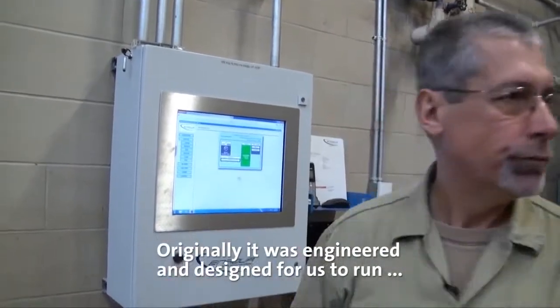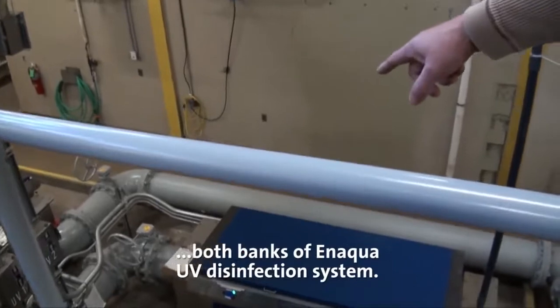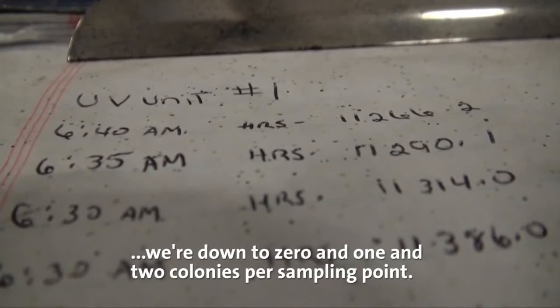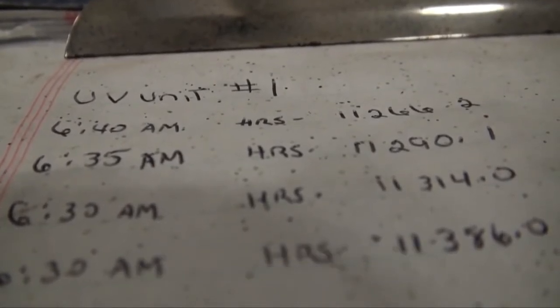Originally it was engineered and designed for us to run both banks of Enaqua UV disinfection system, and as I started testing the fecal colony kill, we're down to zero, one, and two colonies per sampling point.